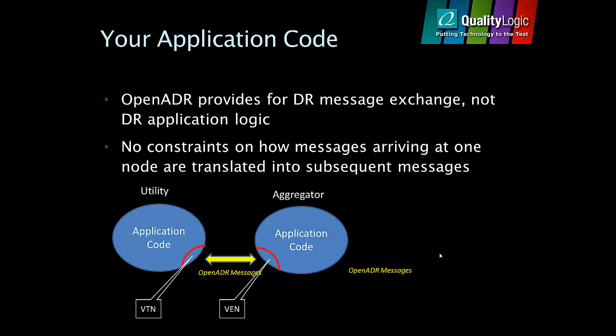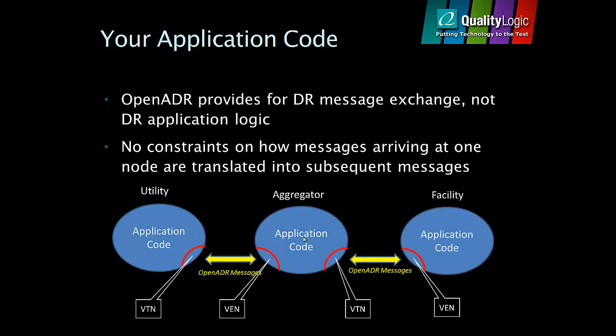For instance, an operator at the console of a demand-response management system at the utility may initiate an event. The details of the event get packaged into an XML payload and shipped via OpenADR messages from the utility to the aggregator. At the aggregator, the message is unpacked and the details of the demand-response event are pushed up into the aggregator's application, which will decide how to propagate the information downstream. The process repeats itself as the message is sent from the aggregator to the facility. The job of OpenADR is to deliver the message, not to decide what to do with it.